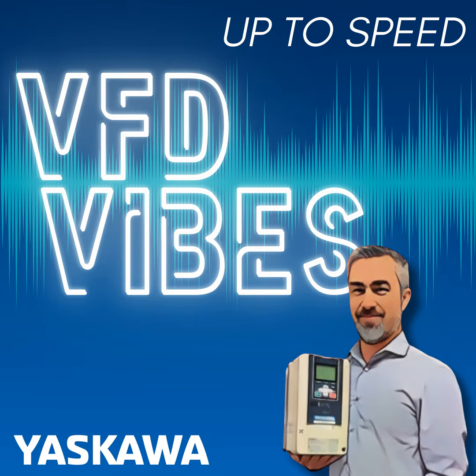Gotcha. So when we talk about connecting the drive to the motor, though, and again, there's discussions around shielded cable, VFD cable. What are your thoughts on those? Well, I usually recommend that customers run 4 wires out to the motor, 3 conductors for the 3 phases from the drive, and a ground wire, an insulated ground wire, through a plain old steel conduit, which is tied to the cabinet and tied into the motor, and that's it. Okay, that's sufficient to protect the conductors.